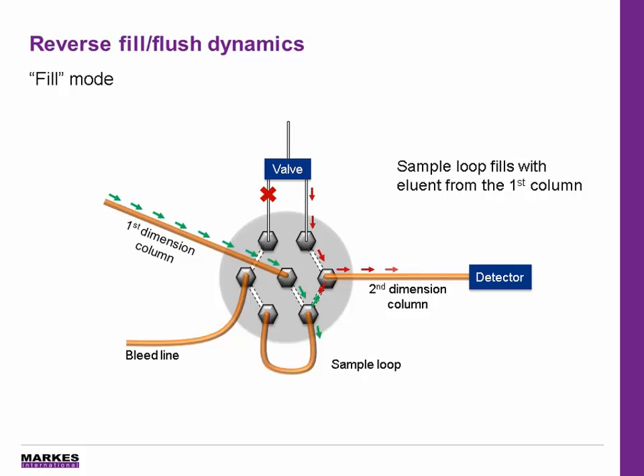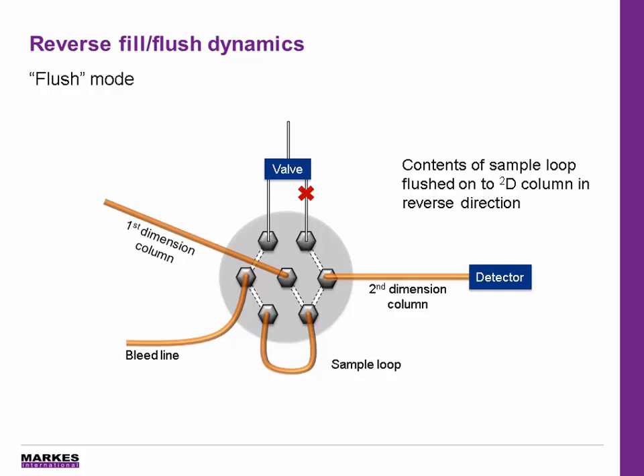The Insight Flow Modulator in this system works using reverse fill-flush dynamics. In fill mode, the modulation valve is configured to allow the first column eluent to fill the sample loop. Any overfilling of the loop goes to the bleed line, rather than causing the second dimension tailing that can be seen with forward fill-flush devices. The various sample loop dimensions are provided with the modulator to allow more flexibility in method optimization by allowing a wider range of column combinations. The modulation valve then switches and the contents of the sample loop are rapidly flushed in the reverse direction onto the second dimension for further separation.